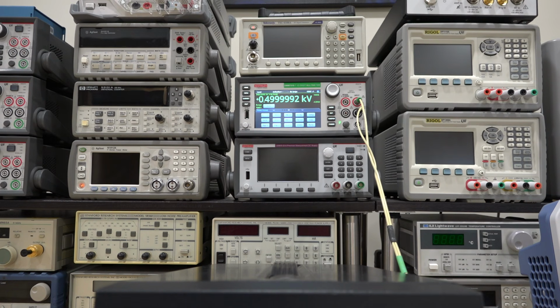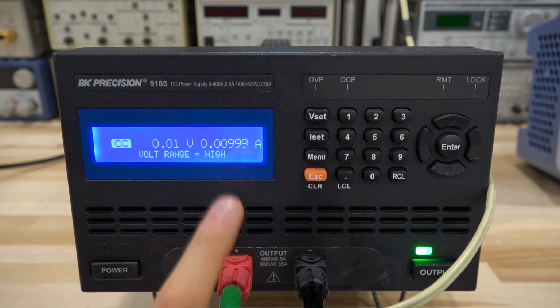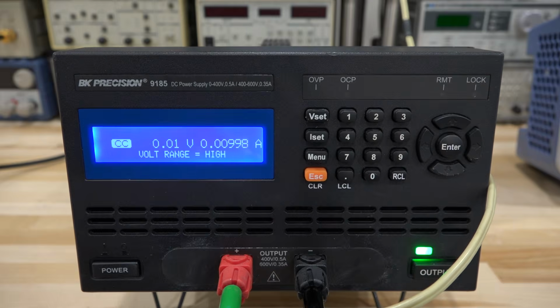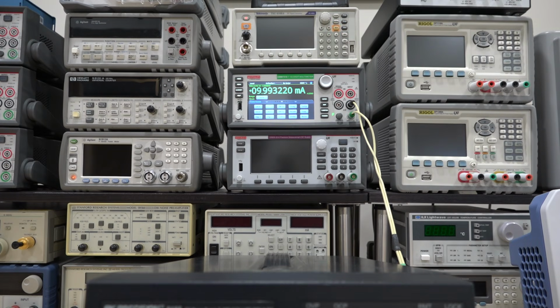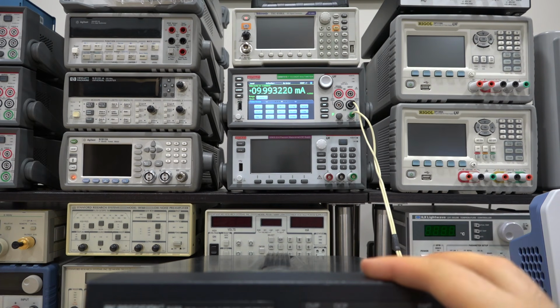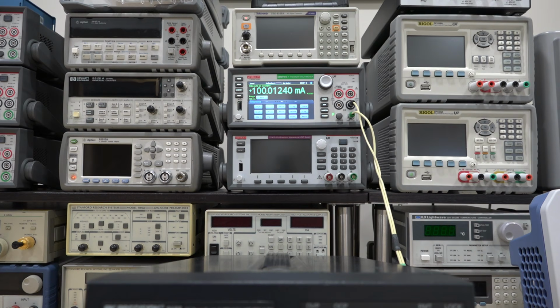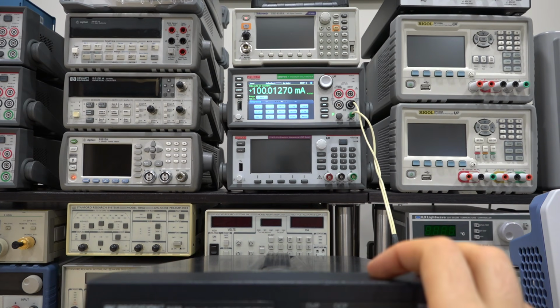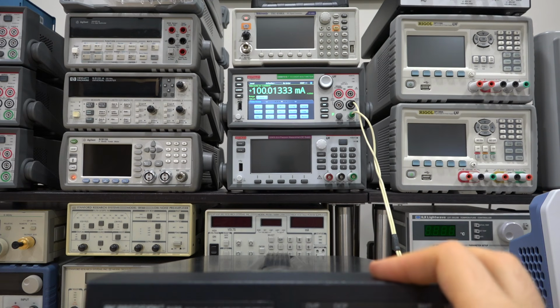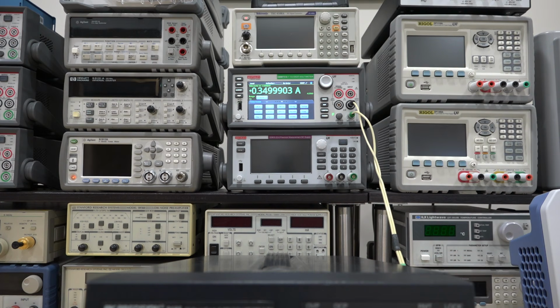So it looks good. Now the only other thing to check is to make sure the current is working, and that will be it. And here's our current measurement, so I have it shunted. You can see right now the current is set to 10 milliamp, and we're just under 10 milliamp, and of course up there we read almost exactly the same value, so I'm quite happy with it. We can set it to some higher values. Let's set it to 0.1, 100 milliamp. Here's our 100 milliamp, and it's dead on, exactly as you would expect it to be. And the highest one that I can set right now in this range, I think, is 350 milliamp. We're reading 349.98, and on the instrument we are basically reading the same thing.